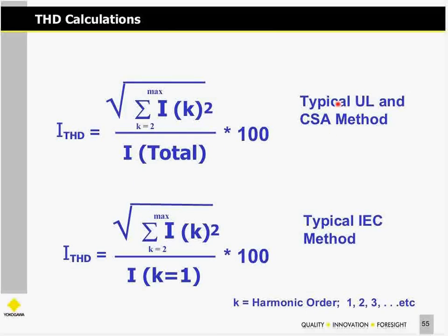The typical UL or CSA method here for North America is the square root of the sum of the squares of the current harmonics, and we divide by the total RMS value. When we're dividing by the total, this number usually does not exceed 100%.